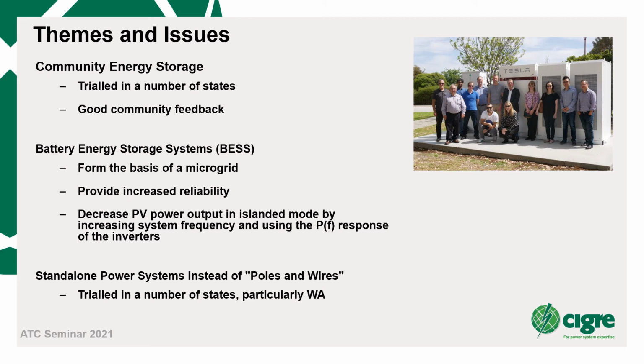One issue with such microgrids is in islanded mode in systems with a large amount of rooftop PV. There is the possibility of the PV overcharging the batteries or possibly exceeding the power rating of the BESS converter. One technique that has been trialled in at least a couple of microgrid installations to manage this issue is to make use of the response of the PV inverter to a change in frequency. When power or charge limits are about to be exceeded, the BESS can increase the system frequency and drive the power output of the PV inverters lower. This can do away with the need for an expensive distributed control system.